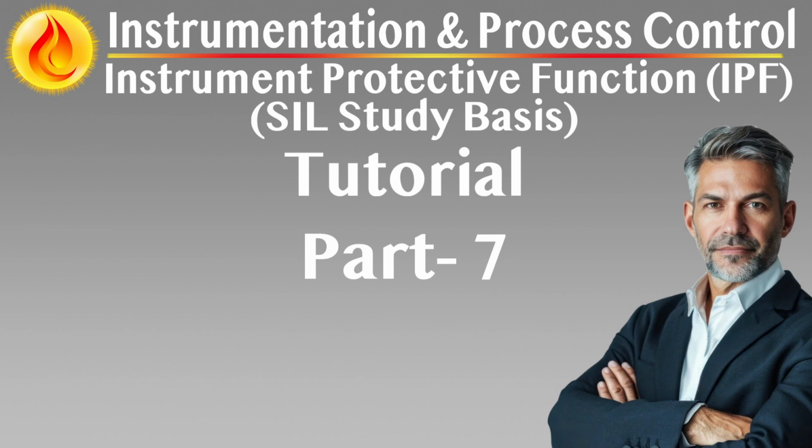Confirmation dialogues and justification logs. If an HMI permits override activation, e.g. for automatic maintenance override switches, the interface must include confirmation prompts, justification entry fields, and role-based access control. Guided override workflow. Where applicable, the HMI should guide users through the override procedure, including validation of process readiness, selection of affected equipment, and expected actions after maintenance is completed.